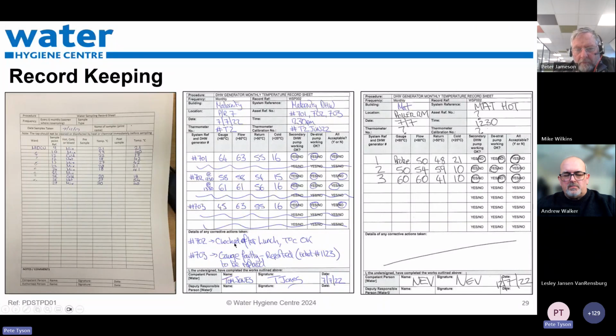Why not? 702 checked after lunch - that was slightly low at 58 degrees. Checked again after 1:30 and it was 61 degrees C, therefore it's all satisfactory. 703, gauge faulty, reported, ticket item number 1123, to be replaced.